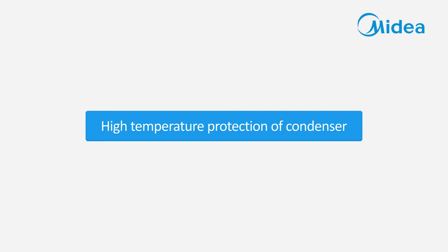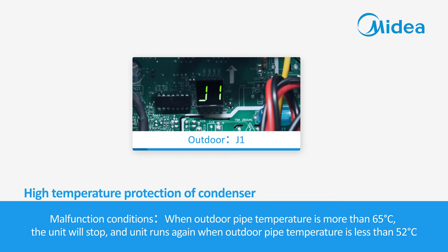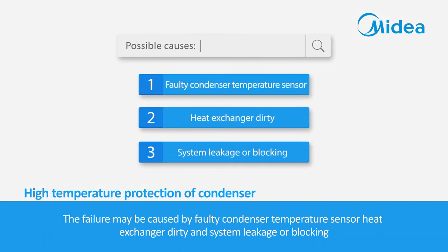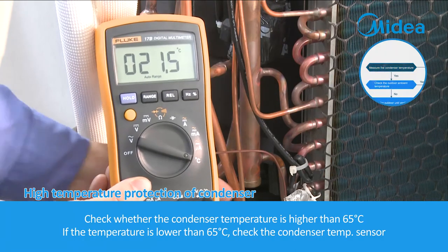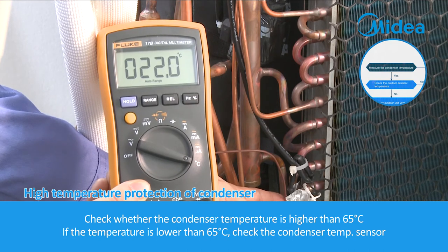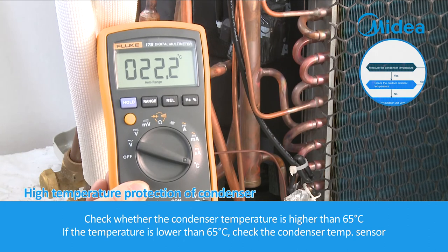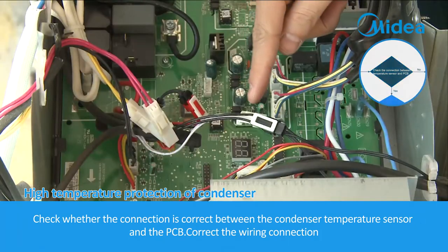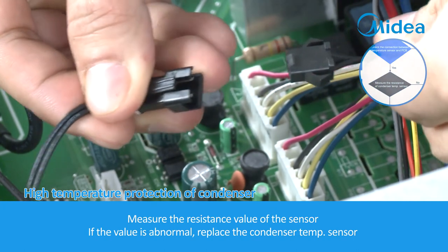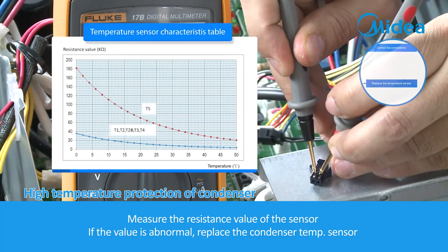High temperature protection of condenser. Malfunction conditions: when the outdoor pipe temperature is more than 65 degrees Celsius, the unit will stop, and runs again when the outdoor pipe temperature is less than 52 degrees Celsius. The failure may be caused by faulty condenser temperature sensor, dirty heat exchanger, or system leakage or blocking. Check whether the condenser temperature is higher than 65 degrees Celsius. If lower, check the condenser temperature sensor connection and correct the wiring. Measure the resistance value; if abnormal, replace the condenser temperature sensor. If normal, replace the outdoor main PCB.